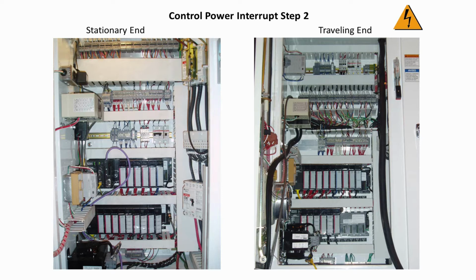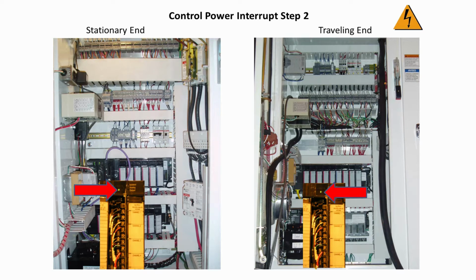Check number 5. If all 3 lights are on all the power supplies at both ends, then, on the stationary end, locate the bottom PLC rack. In slot number 4 is the relay output module that turns on CR1. On the traveling end, locate the bottom PLC rack. In slot number 2 is the relay output module that turns on CR2. On both modules, the number 5 LED in the B row of numbers should be lit on both the stationary and traveling ends. The output wire number that connects from the relay output module to CR1 on the stationary end is Q237, and the similar wire on the traveling end is Q253.